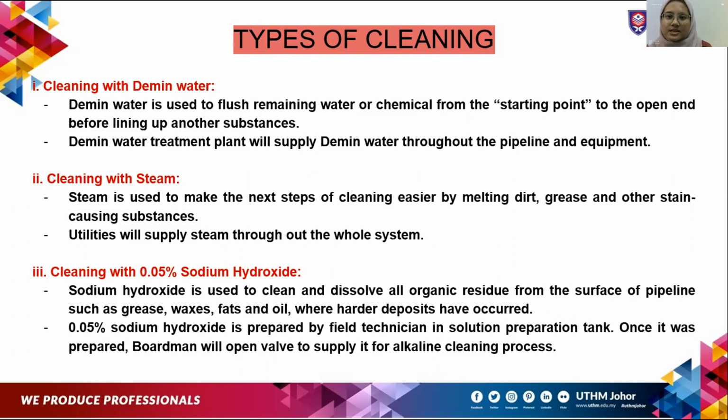The next type of cleaning is cleaning with 0.05% sodium hydroxide. Sodium hydroxide is used to clean and dissolve all organic residue from the surface of the pipeline, such as grease, wax, fats, and oil, where harder deposits have occurred. This 0.05% sodium hydroxide is usually prepared by the field technician in the solution preparation tank. Once it is prepared, the Boardman will open the valve to supply it for the alkaline cleaning process.